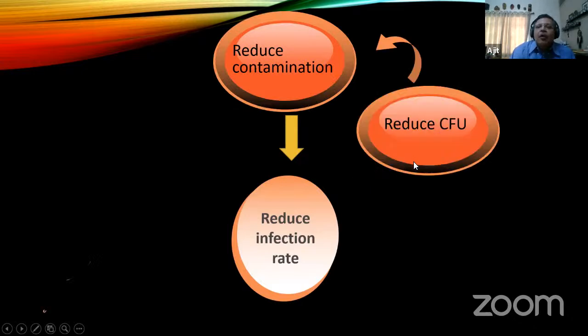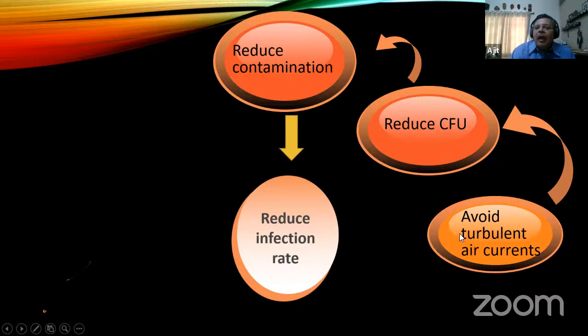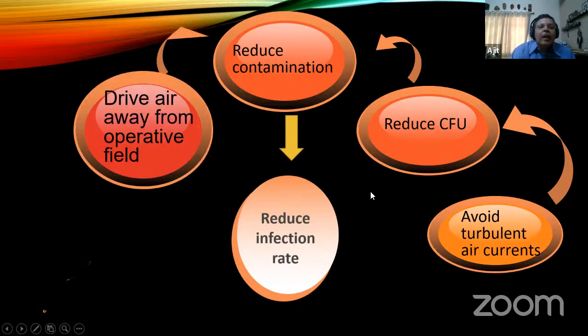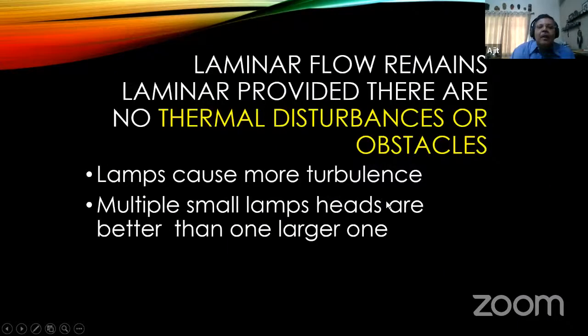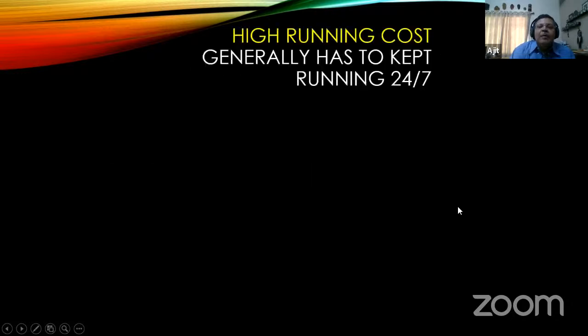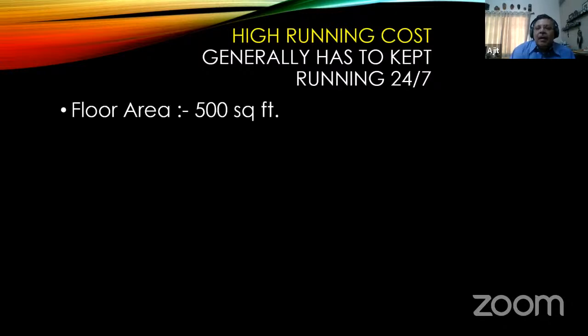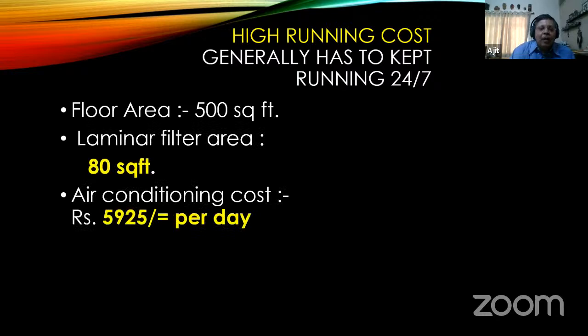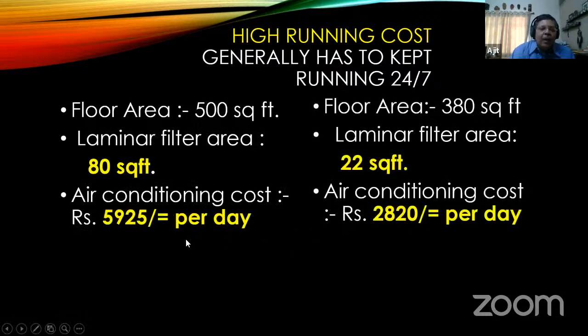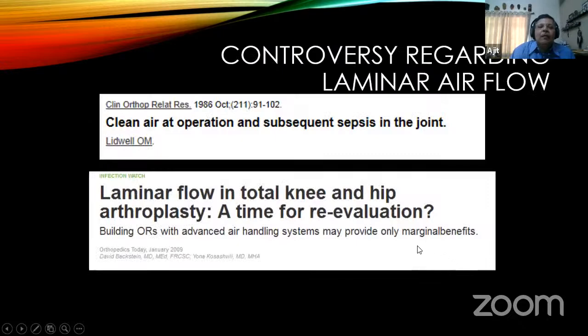You have to reduce the colony forming units by avoiding turbulent air currents, and we have to drive air away from the operating field. So you need a laminar airflow directly on the operation theatre field. Now, this remains laminar as long as there are no thermal obstructions or disturbances. So, lamps are an important obstruction to that. The laminar airflow has a very high running cost, which you have to consider when you are running a hospital. For a big operation theatre, it might be as much as 6,000 rupees per day, and for a small OT, it will be 3,000 rupees per day.